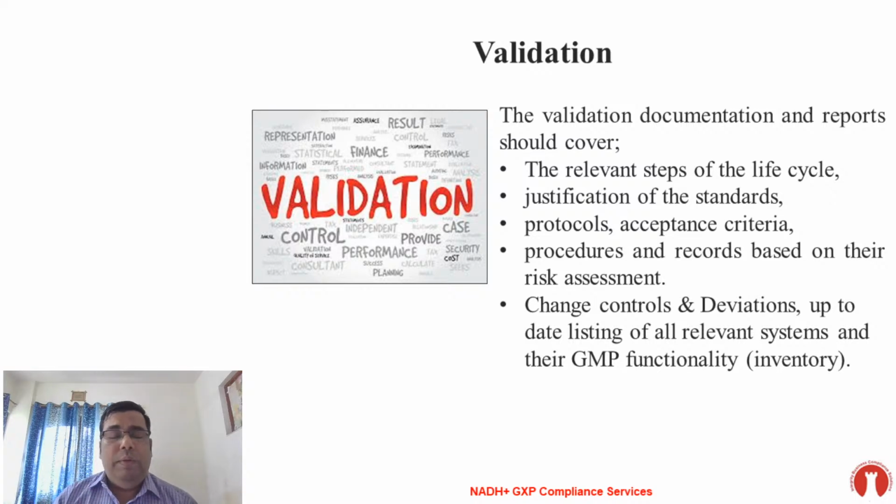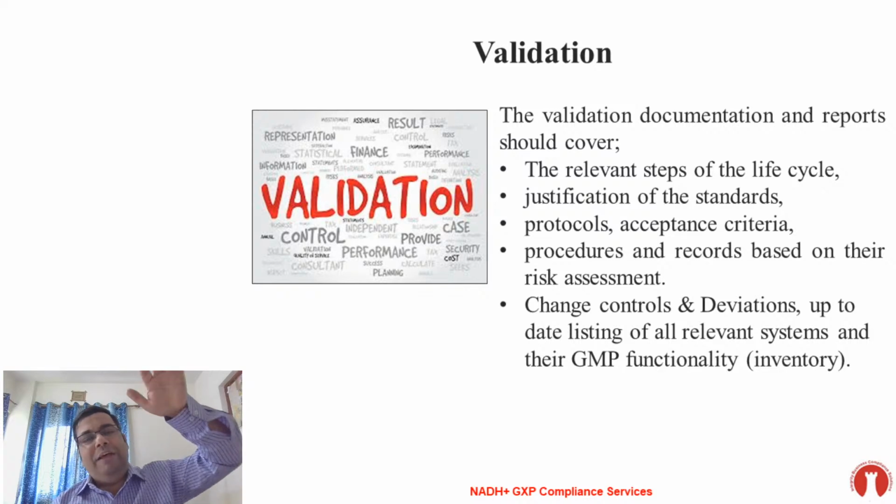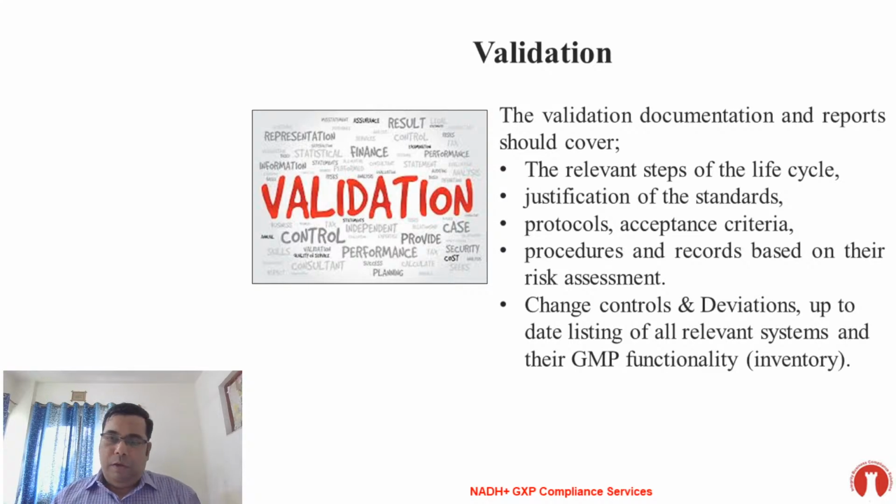Because validation is done by a third party, the activity is done, a lot of files are filed, and then the sign off, and then they are kept separately. But when inspection is there, the system owner or the process owner or even the people who are facing the inspection are not able to reply to the inspectors with respect to the validation, what is the strategy and what is the depth of validation and all these questions. And that is the reason the companies are getting the observation.